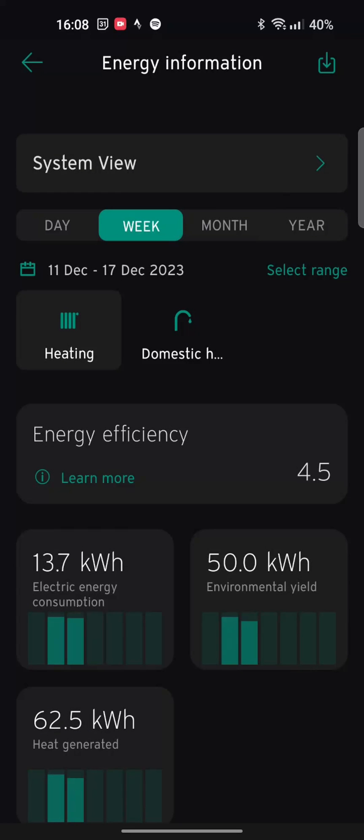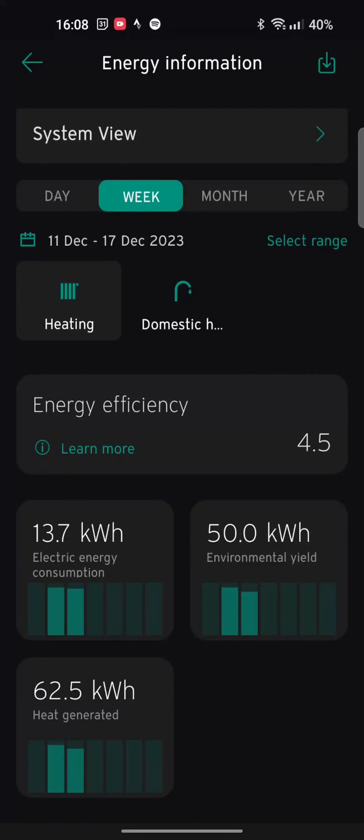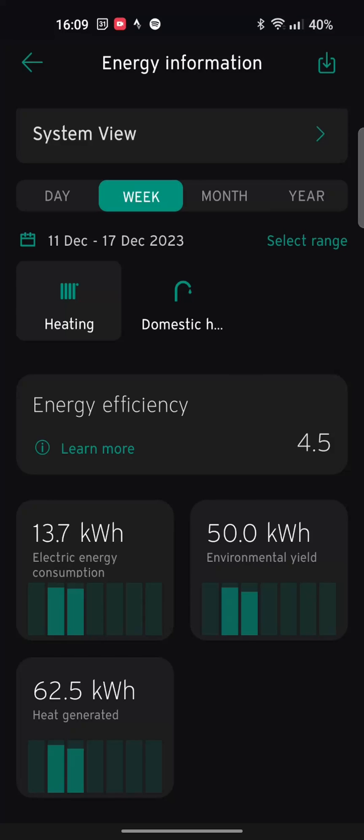One of the things that a lot of people like, I'm not really that fussed. It shows that my COP is 4.5. That's the energy efficiency bit that says 4.5. And then it can show you how it's calculated. So we've got the 13.7 kilowatt hours of electric energy consumption. This is just the past two days. And then 50 kilowatt hours that's come from the environment and brings that up to a total of 62.5. Clearly, this app can't do any maths because 13.7 plus 50 is not 62.5.